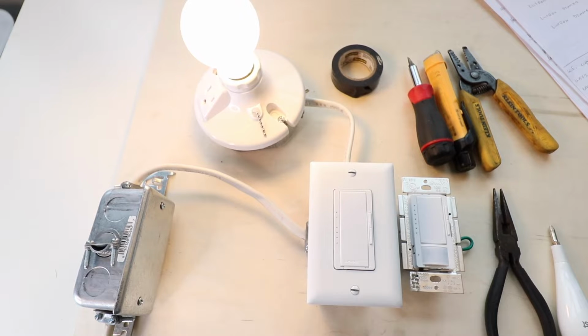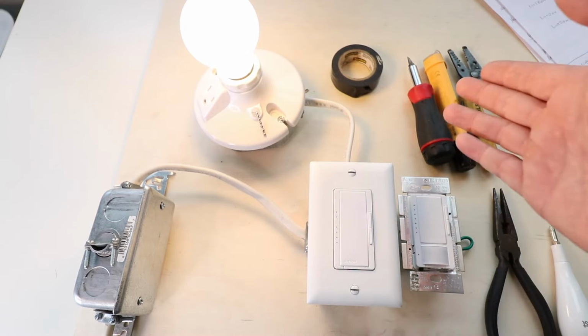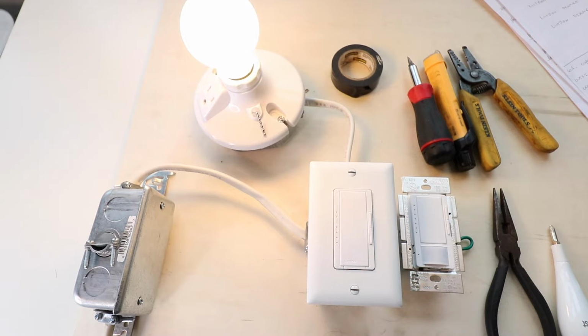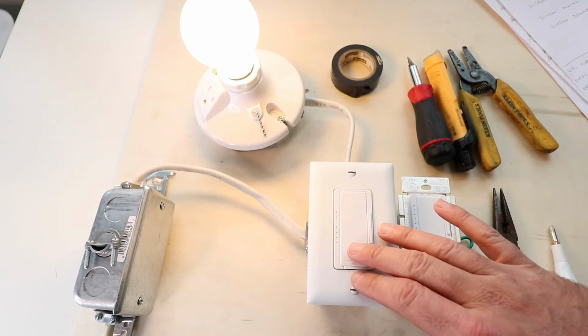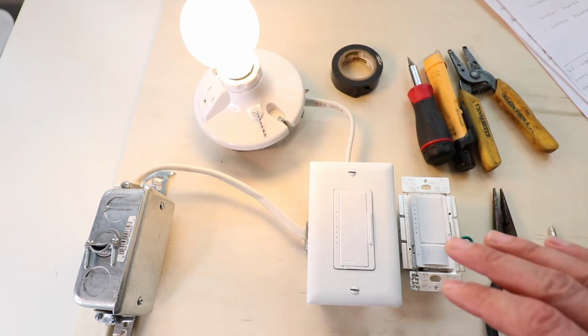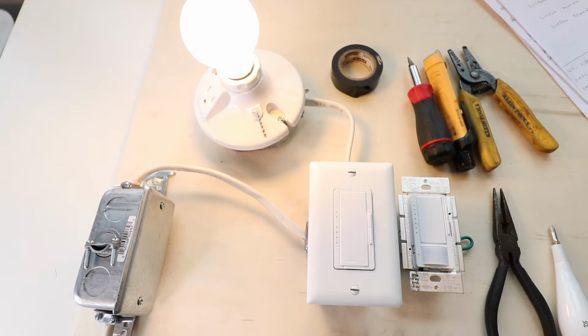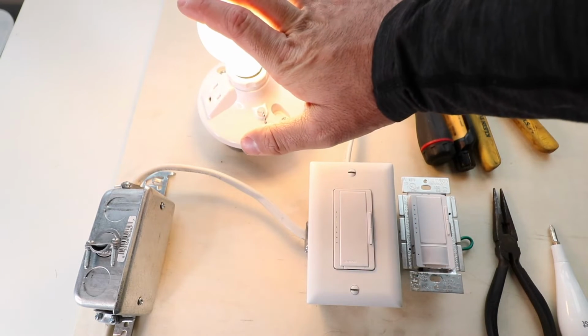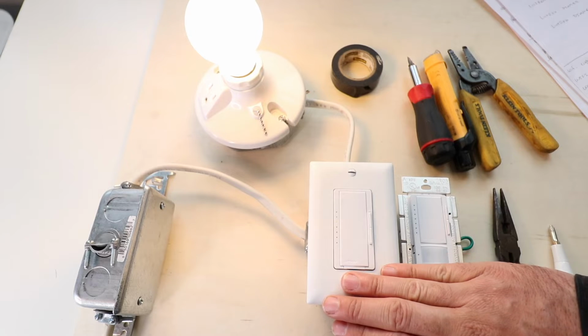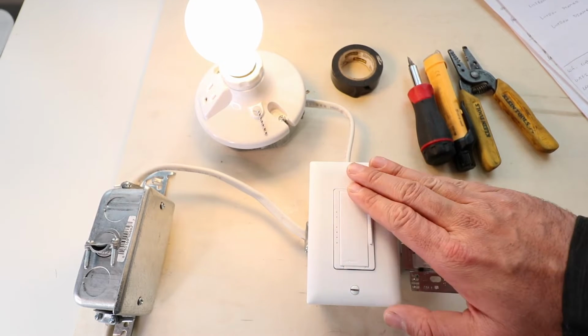So in order to install one of these, first you need to turn off the power to the light switch. I'm going to turn on the light switch physically itself, then go down to your junction box or electrical panel and turn off the circuit breaker for this particular light switch. I like to have the light on when I do this, so that when I turn the power off at the breaker, I know it's off because the light is no longer on.